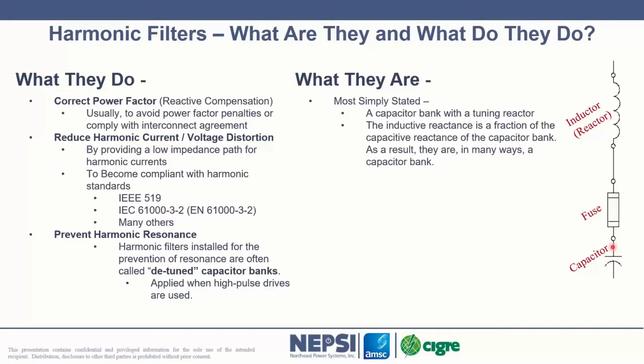The next reason it is installed oftentimes is to prevent harmonic resonance. I kind of have these out of order, unfortunately, but oftentimes harmonic filters are put in because you have to do power factor correction, but you want to prevent resonance. So a customer comes to us, they need reactive compensation, they're trying to avoid a power factor penalty, and they look to install power factor correction. They do a resonance analysis, they do a harmonic analysis, and that harmonic analysis determines that yeah, I've got a resonance issue. Well, you put the filter in to prevent resonance. That is the second reason why most filters are installed.